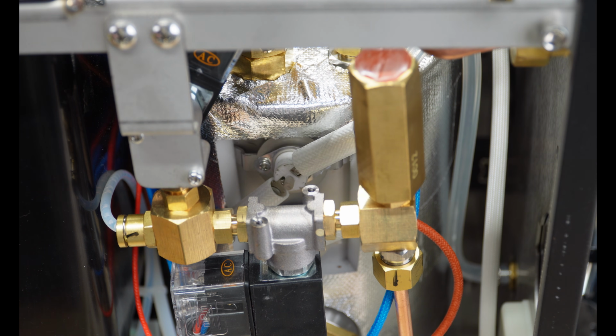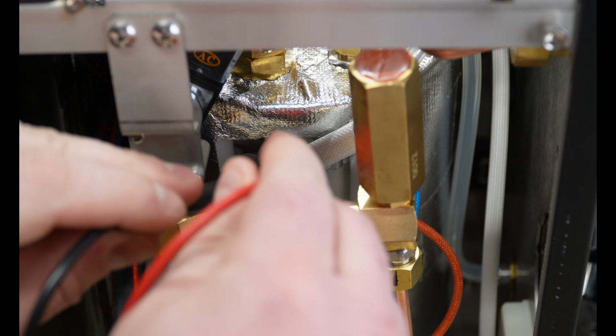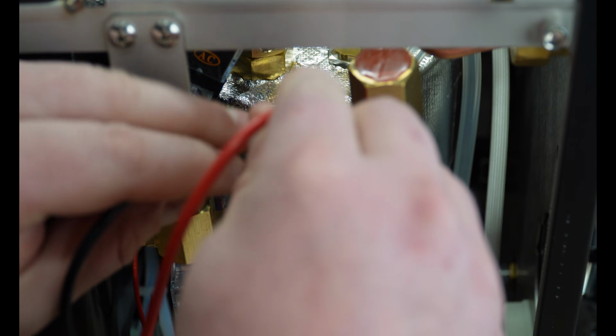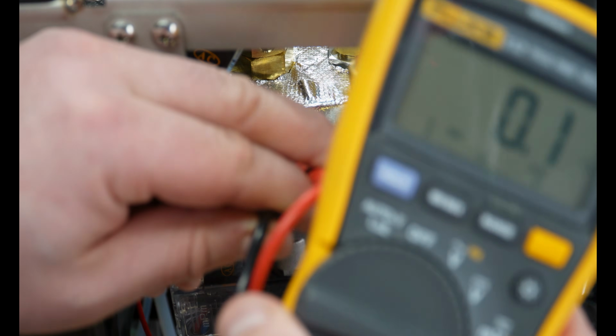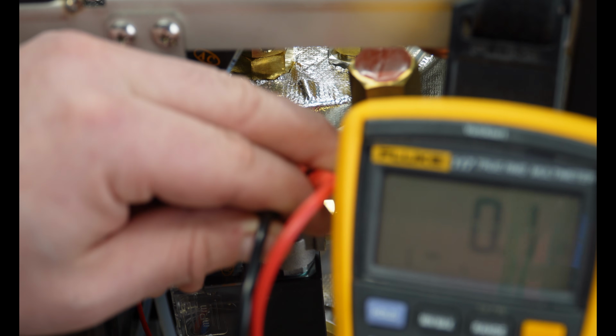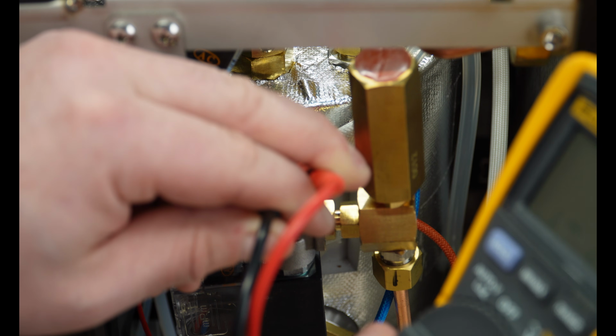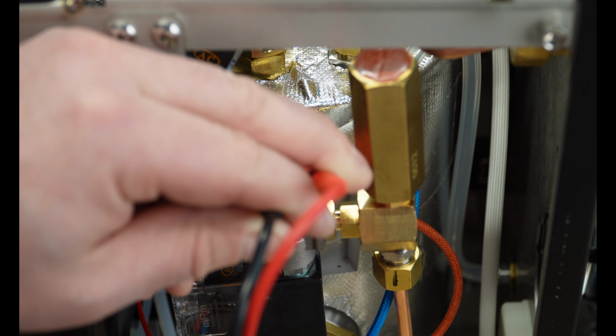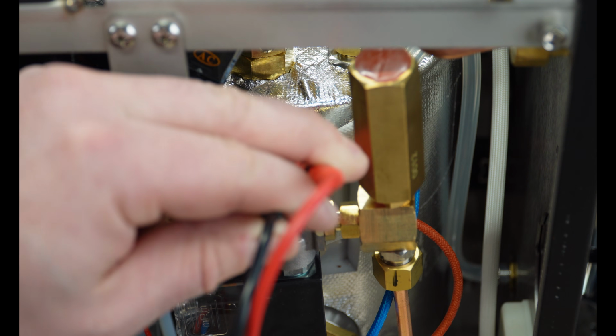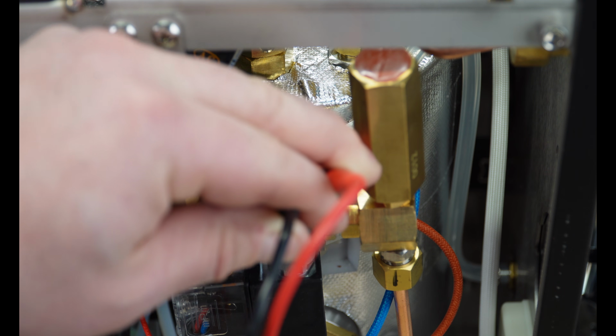Next, these do go bad from time to time. I'm going to put my probes on, and this one is closed, so if the button's pushed in, we should get a very low ohm reading. Sorry if I'm a little bit too close. It's 0.1 ohms, so it should be very low. It shouldn't be open line. It should just show that it's passing through. So that's the next thing that I would check.